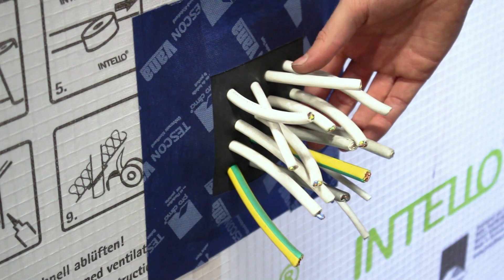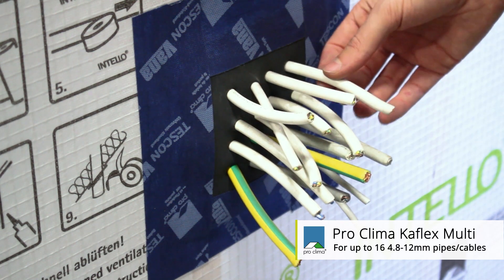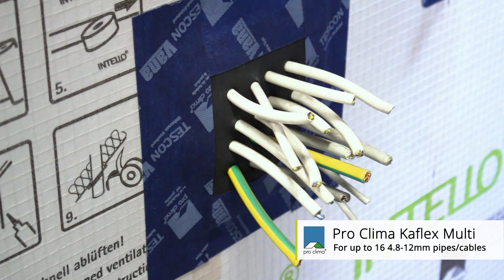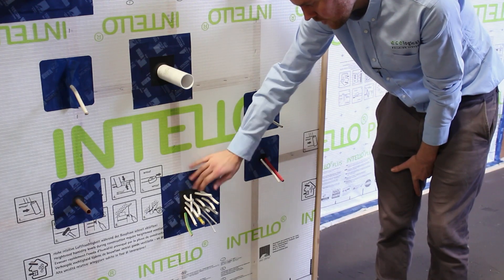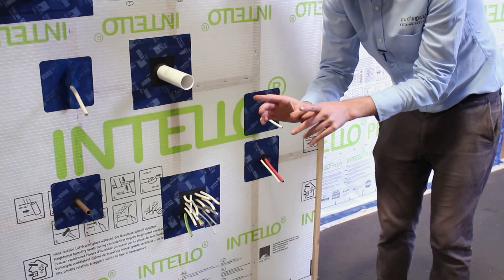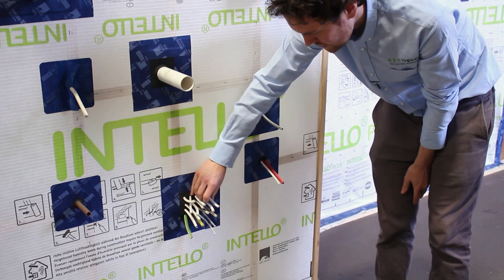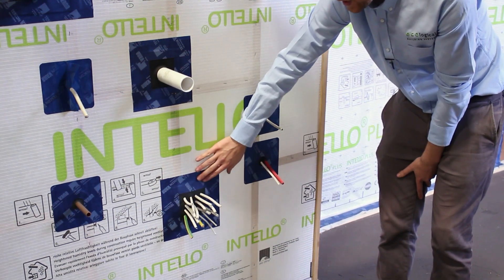The other useful grommet is the Kaflex Multi, which allows you to fit multiple cables in one area. It's supplied as a 150 by 150mm patch of EPDM, with a punch supplied with the patch. You punch in where you think the pipes are going to penetrate, keeping the pipes and cables at least 10mm apart, and you can feed up to 16 cables through the patch and seal the EPDM patch back to the air barrier.